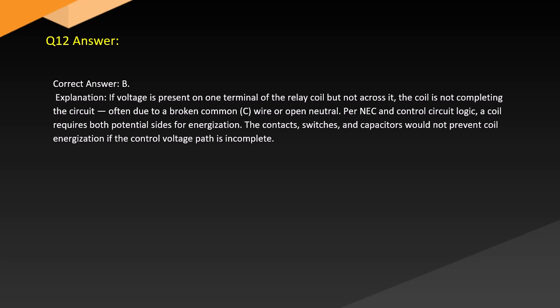Answer. Correct answer: B. Explanation. If voltage is present on one terminal of the relay coil but not across it, the coil is not completing the circuit, often due to a broken common or open neutral. Per NEC and control circuit logic, the coil requires both potential sides for energization. The contacts, switches, and capacitors would not prevent coil energization if the control voltage path is incomplete.